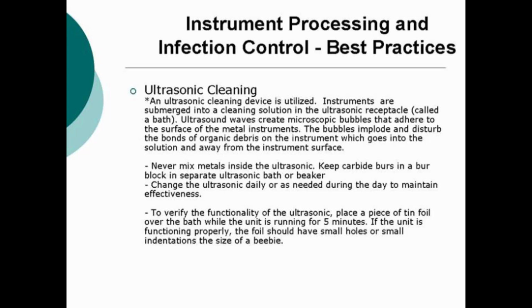As discussed, we never want to mix metals in the ultrasonic cleaner. Keep carbide burrs and a burr block in a separate ultrasonic bath or beaker. We want to change the ultrasonic bath daily or as needed during the day to maintain effectiveness. An efficient way to verify the functionality of the ultrasonic cleaner is to place a piece of tin foil over the bath while the unit is running for 5 minutes. If the unit is functioning properly, the foil should have small holes or small indentations the size of BBs.